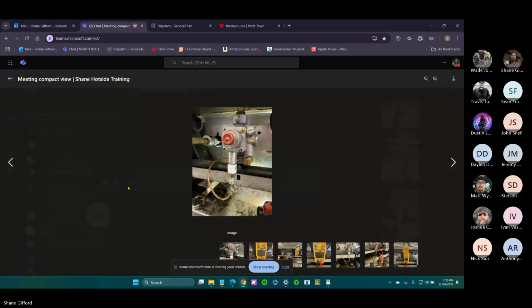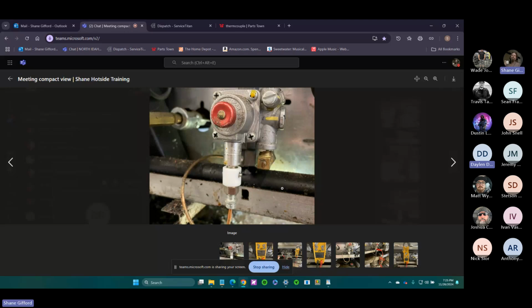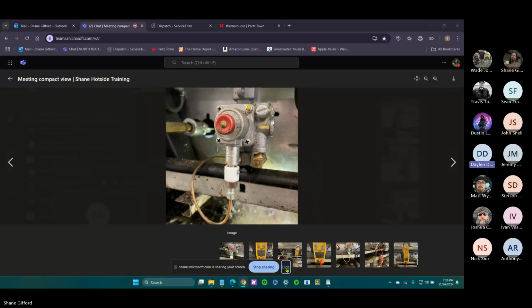So a lot of the times, depending on the manufacturer, they're in really tight spots, and sometimes past techs will bend metal or some way or another you're not able to get to all the connections for your gas, your inlet and outlet. So what I was taught is you don't actually have to take that whole body out. You take those 4 Phillips screws out, and that head will pop out. There's a little spring, and another part in there. You can pop that head out, pop a new one in, and it should be good to go because everything else behind that is just the body.